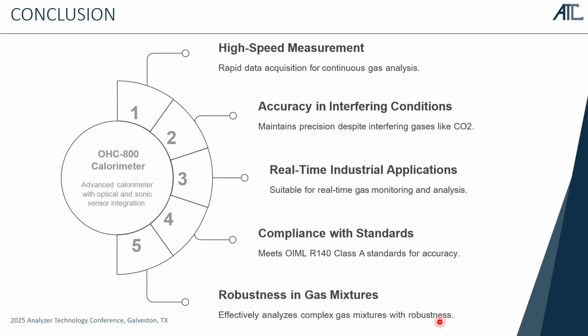All right, so this is the last slide, the conclusion on the optosonic sensor. We have a high-speed measurement, T90 within 5 seconds. And we have 2% accuracy for the flare stack application, and some others at 1%. It is a real-time measurement, and you don't need to worry about calibration in the field for more than 10 years.